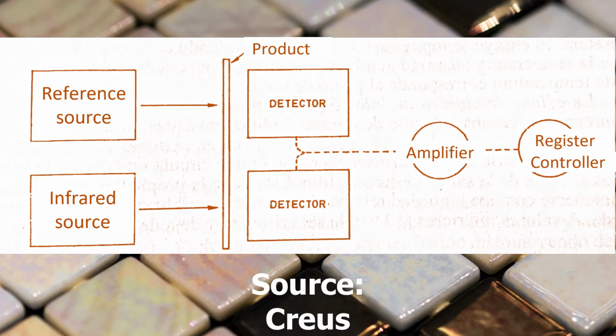For the measurement to be independent of the layer of air sandwiched between the emitter, the material, and the detector, of the variation in the thickness of the material and its relative position between the emitter and the detector, it is customary to use an additional source that acts as a reference. The emitter-detector assembly is usually mobile in order to scan the entire paper web.